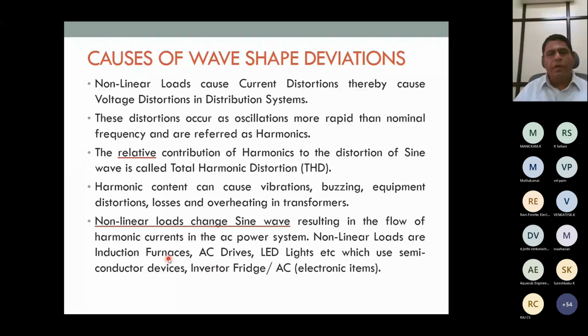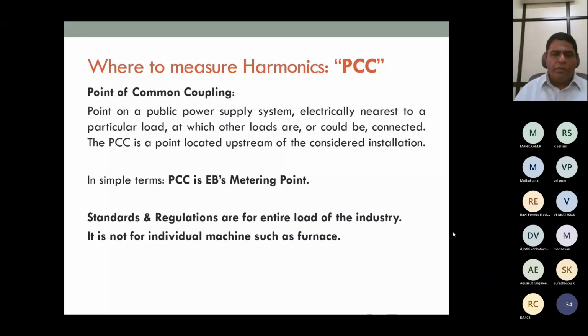Harmonics are measured by a term called total harmonic distortion. It is the relative contribution of harmonics to the sine wave. Harmonics can cause vibrations, buzzing, equipment distortions, and overheating. I have already given examples of nonlinear loads. Go to the next topic: where to measure harmonics?